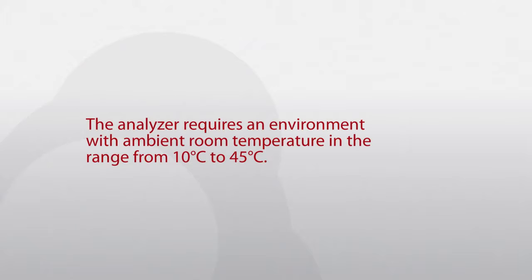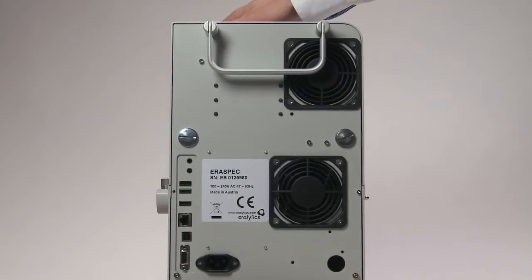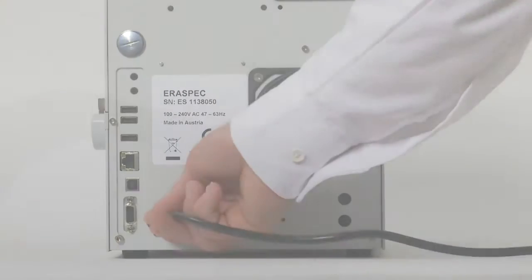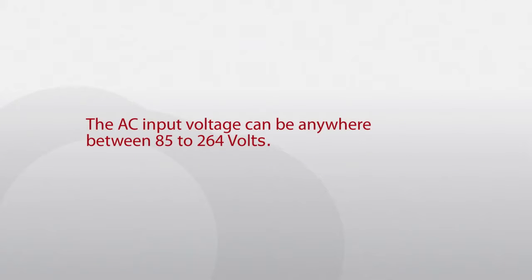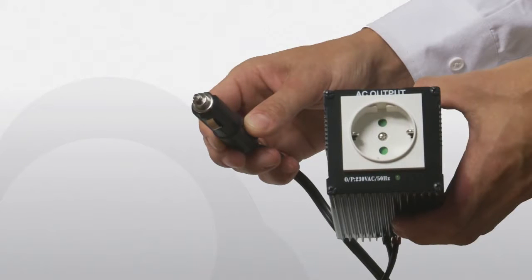Turn the instrument and connect the power cable to the plug on the rear side of the instrument. The AC input voltage can be anywhere between 85 and 264 volts. If the instrument is used in mobile laboratories or in the field, it can also be operated at 12 volts DC using a DC to AC converter.